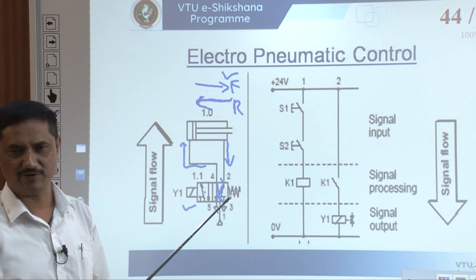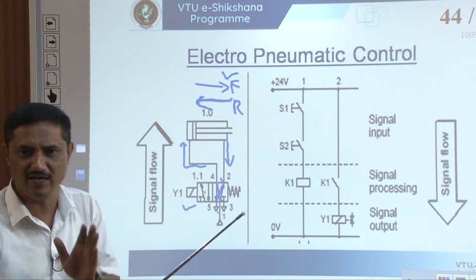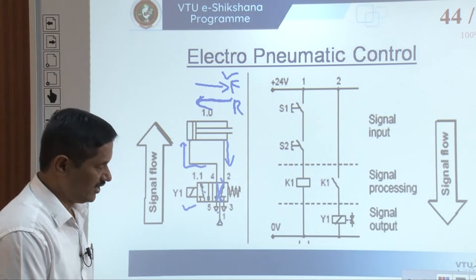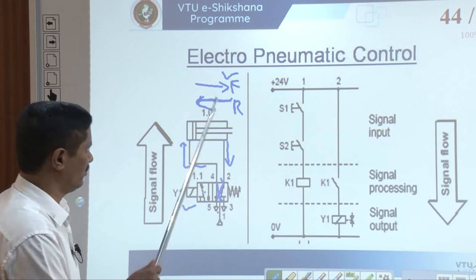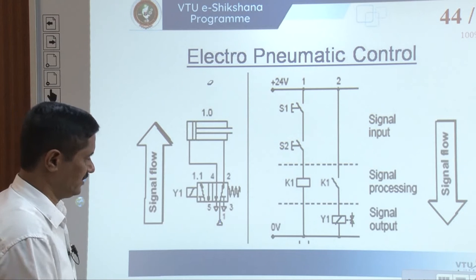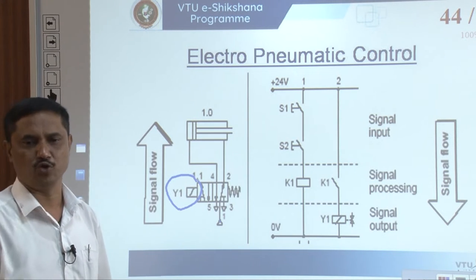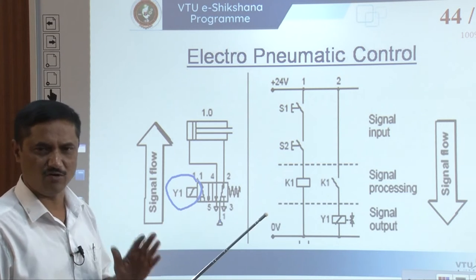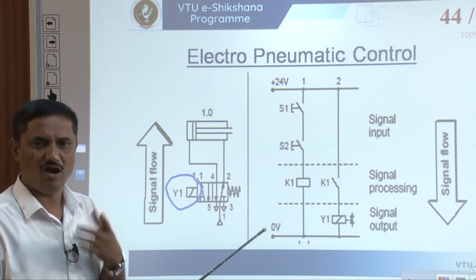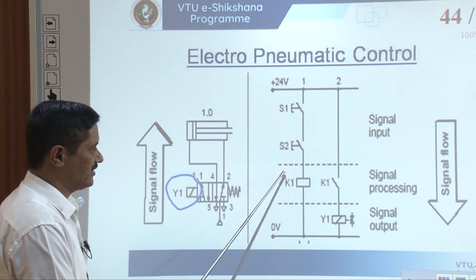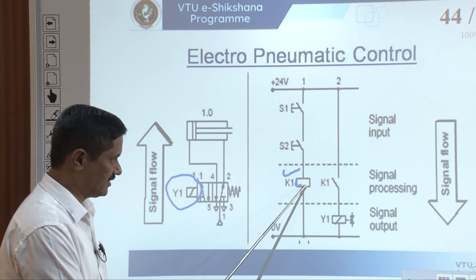Now consider the corresponding electrical circuit using AND logic. The output element Y1 is the solenoid, and we use one relay K1 to energize it. The relay coil K1 is placed in line 1. We take switches S1 and S2 — both normally open — connected in series. If you press S1 alone, current can flow only up to S1 since S2 is still open, so the relay coil does not get power. You must press both S1 and S2 for current to reach the relay coil — this is AND logic.